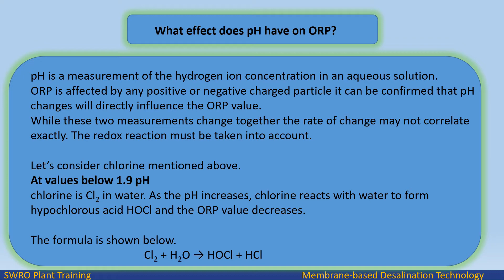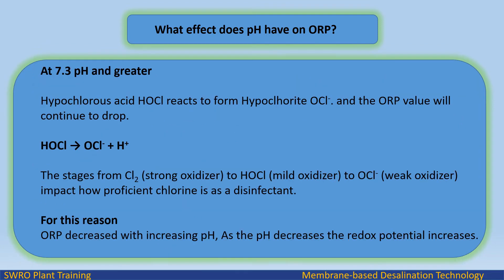Consider chlorine: at values below 1.9 pH, chlorine is Cl2 in water. As the pH increases, chlorine reacts with water to form hypochlorous acid HOCl, and the ORP value decreases. The formula is: Cl2 + H2O → HOCl + HCl. At 7.3 pH and greater, hypochlorous acid HOCl reacts to form hypochlorite OCl⁻, and the ORP value will continue to drop. The stages from Cl2 (strong oxidizer) to HOCl (mild oxidizer) to OCl⁻ (weak oxidizer) impact how proficient chlorine is as a disinfectant.